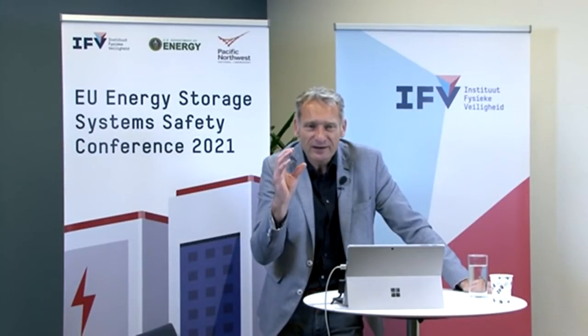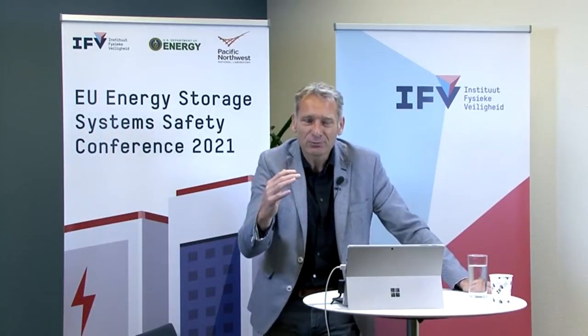And the final question which came up to my mind when I saw your slides: you showed that some of the debris was rocketed over 22 meters. Are there guidelines in your country with thresholds for the amount of debris and the distance it may travel as a result of an explosion? Great question. In the current published codes, no. In 855, it's currently being revised for the next edition, and we are including the term cabinets, because that was not included before. As part of the explosion protection for cabinets, there is language stating that none of the cabinet equipment shall become projectiles or be dislodged in the event of an explosion.